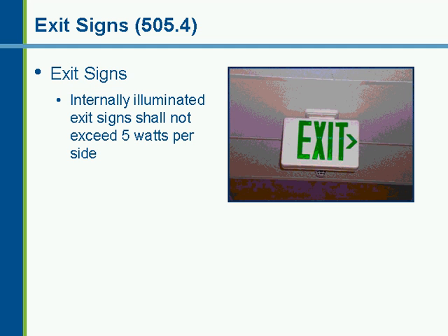One other small requirement is for exit signs, and the simple requirement is that internally illuminated exit signs shall not exceed 5 watts per side.